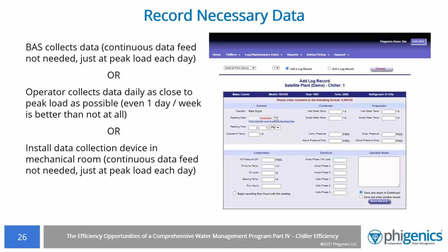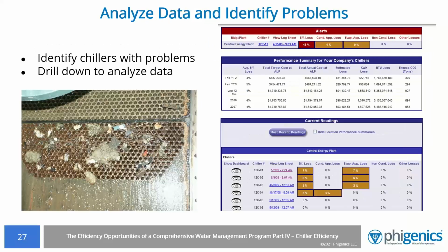So, first, you need to collect the necessary data. You don't need thousands of data points. In fact, you can get by with just one set of readings a day at or near peak load. And you can even do it manually, but you do need a place to store the data. Next, you need to perform some calculations and then analyze the results. This will enable you to begin to identify where you may have problems, such as this picture of a tube bundle opened up. And no, you should not use your tube bundle as a filter as shown in the picture.